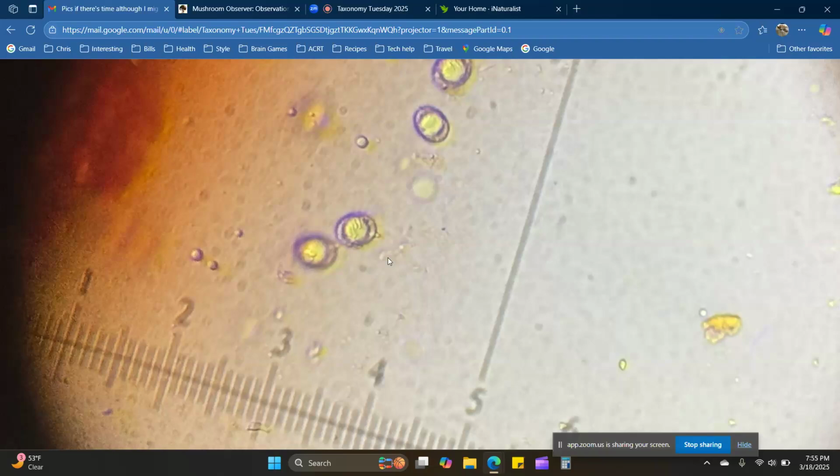It's another little lens, and usually there's a little part that as you turn the switch, it'll shrink radially, so you only have this little tiny point of light as opposed to all the light coming through. As you move that around, it'll contrast differently. It's the condenser, right? Right, the condenser. It has a little lever, and with each magnification, you have to move that lever to either expand or contract the iris, just like in your camera.